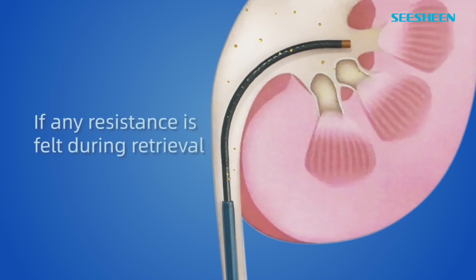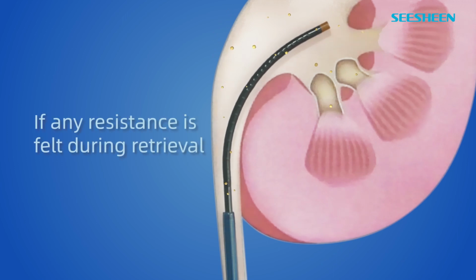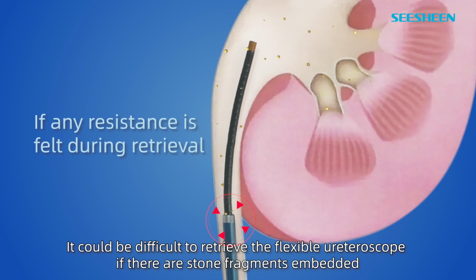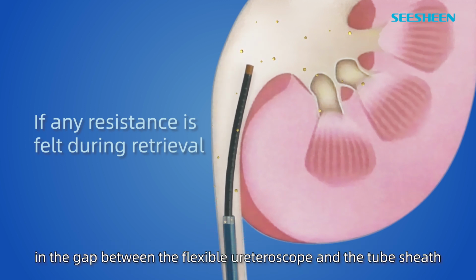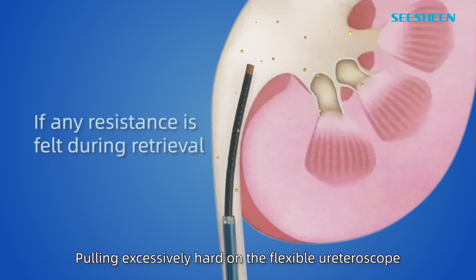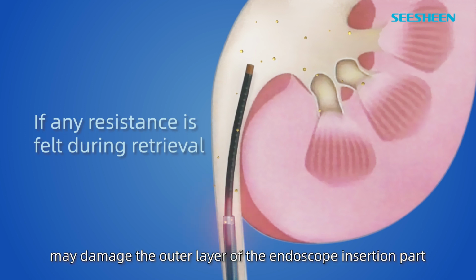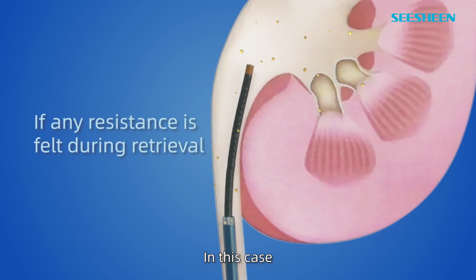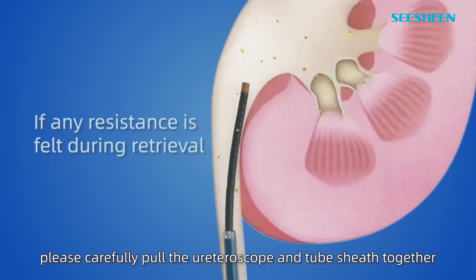If you feel resistance during retrieval, it could be difficult to retrieve the flexible ureteroscope if there are stone fragments embedded in the gap between the flexible ureteroscope and the tube sheath. Pulling excessively hard on the flexible ureteroscope may damage the outer layer of the endoscope insertion part. In this case, please carefully pull the ureteroscope and tube sheath together.